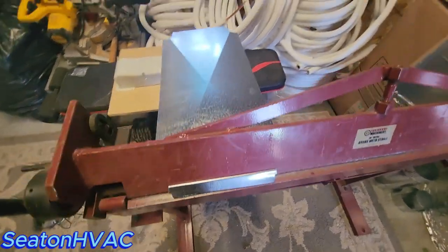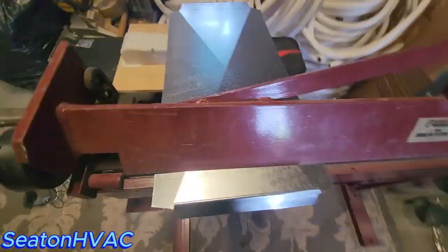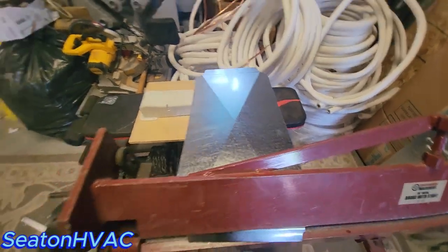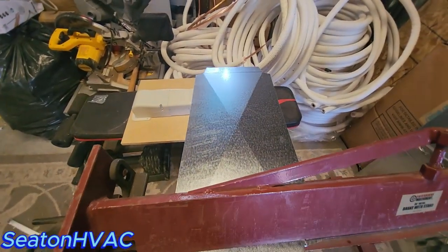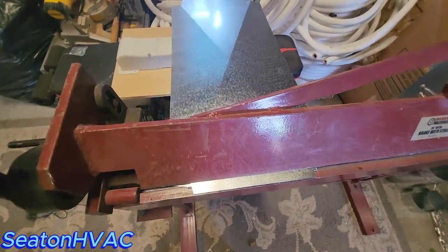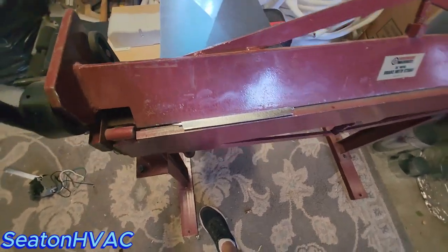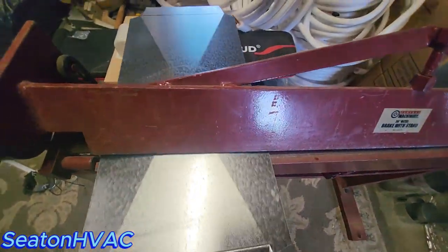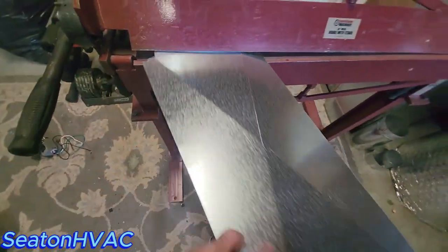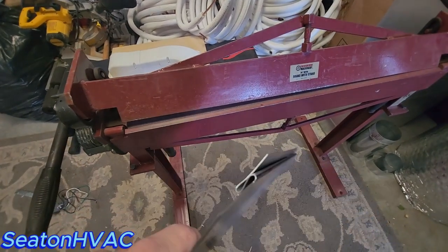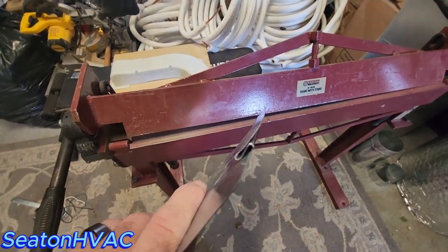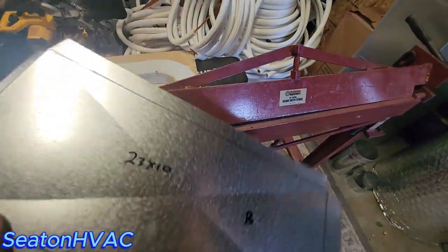You're going to pull that out like so. Okay, then you're going to try to slide that underneath your brake. There we go. Hard to do with one hand, but I got it. Then you're going to smash that down, not too much, because you want to be able to get your metal in there for your pocket. All right, and what you end up with is a perfect Pittsburgh.